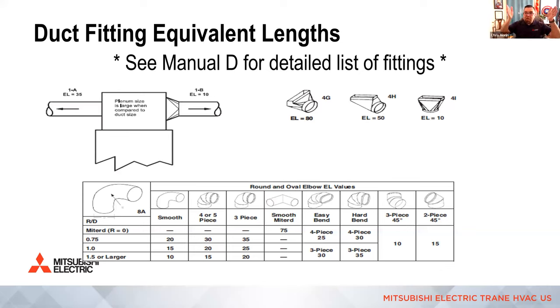This is the top plenum coming off of the top of a vertical system. Even if you flip this horizontally, the same numbers apply, okay? So if you pressurize that box and you just come with a 1A fitting off the side of that box for the trunk, right, stabbing into the side of it, then that's a 35-foot fitting. Believe it or not, that's not bad, okay? Because you're able to pressurize the box and the air can now make that turn. If you make it easier for the air to make the turn, just by having a tapered fitting for the air to make that turn, instead of 35 feet, it could be 10 feet. That's a much lower value. That's only a pressure loss of 0.01. If you guys didn't know, you can accurately express equivalent length with pressure loss just by moving the decimal points. There's a 0.1 pressure loss for every 100-foot fitting.